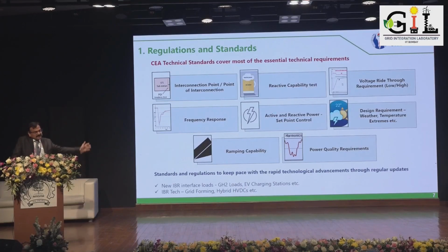Active and reactive power set points, as I've mentioned, can presently be done from the PPC, and the PPC should have the capability to do this remotely, say from the control center. How much time does it take? This is very important, because in the entire control loop, remote operation time will have an impact. Control engineers know that gain and time delay are extremely important, along with pass filters, etc. These things can make the system very sluggish, not up to the mark, or very fast and oscillatory.